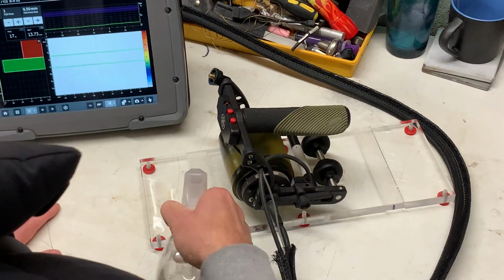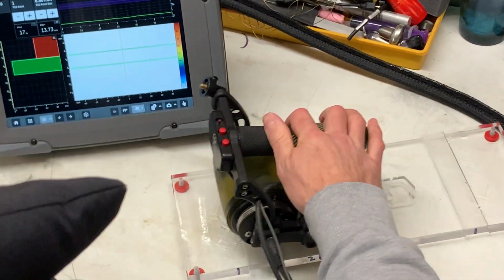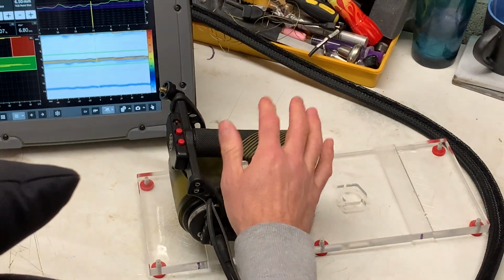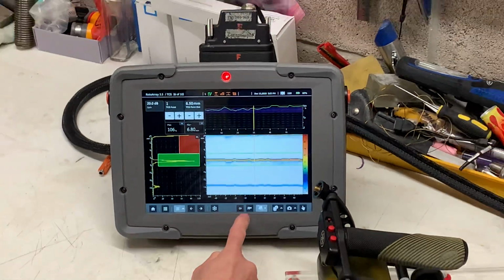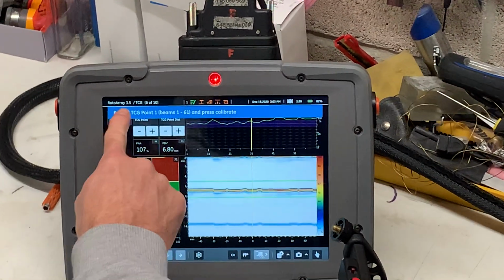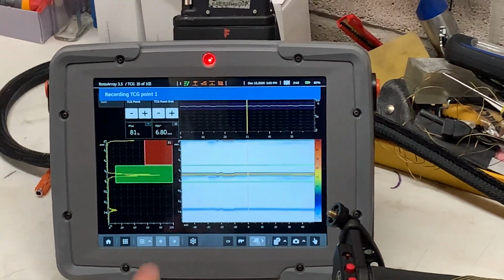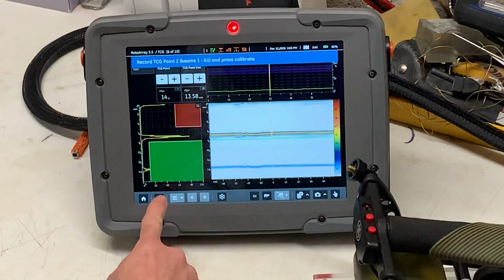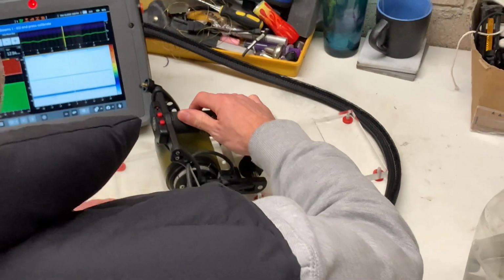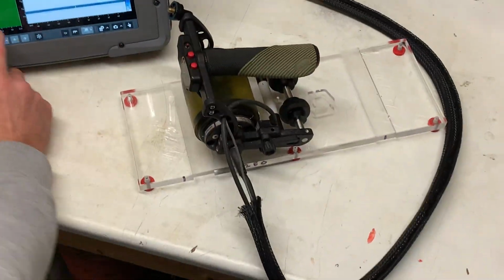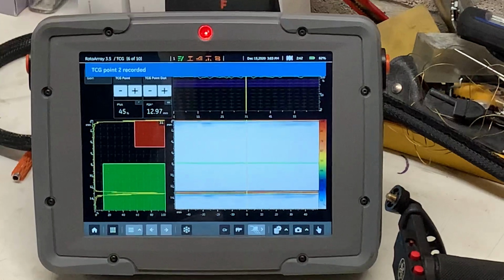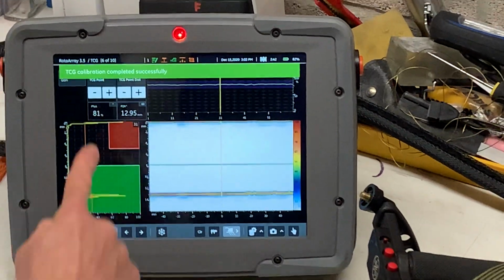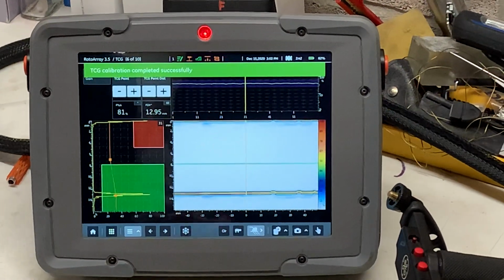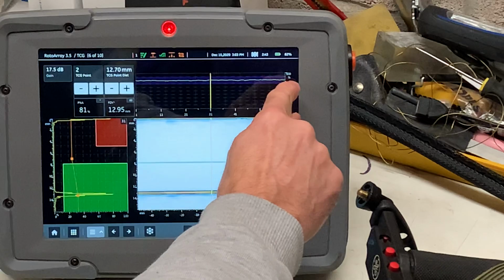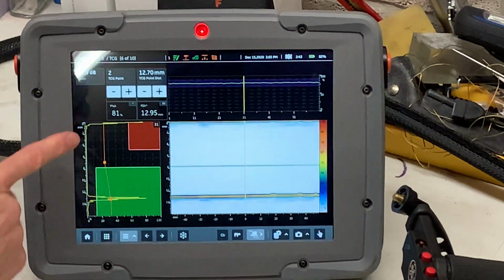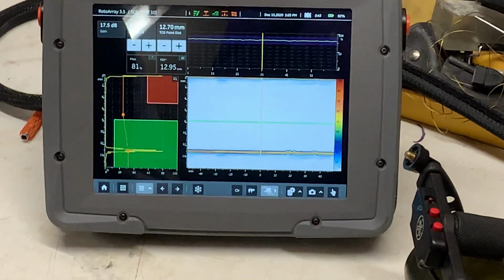Some water on there. Right. So our signal is in the gate at the right position, and we're just going to hit that calibration icon again. Record TCG for point 1. Hit it again. It tells me it's recording. Now it wants me to move to point 2, which is the 12.5, which is just the back of this part. So if I just step off here and step onto it, so it's in the gate, I hit calibrate again, it tells me TCG point 2 recording, and then I get this green banner telling me it's done successfully. Now I can see the amplitude across all my elements is all kind of equal. And it's drawing this dark curve to represent the TCG on the screen.